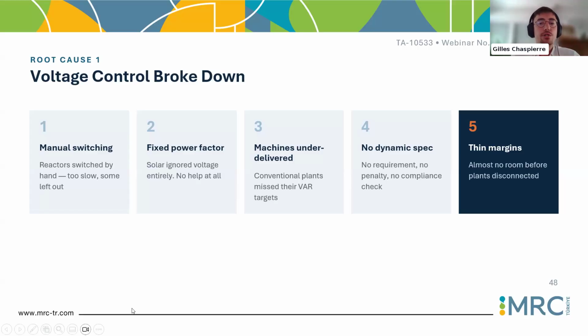And now you have the thin margins. For me, this thin margin is not really voltage control related. It's more protection related. So it can be put in another root cause, but whatever, the message is the same. It's a bit contradictory, but in the Spanish grid code, it is allowed transiently to operate the voltage up to 435 kV, which is very big, transiently. So you cannot stay like this forever, of course. But at the same time, you have generators who disconnect if the voltage reaches 435 kV. So there is a problem there.